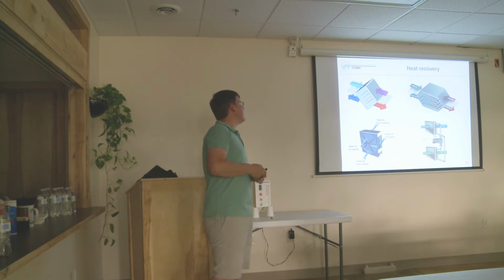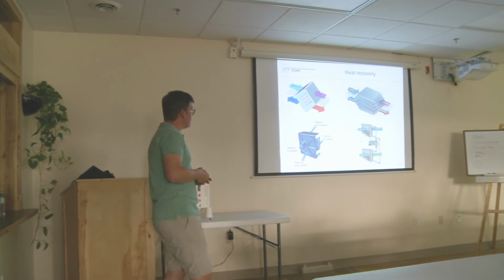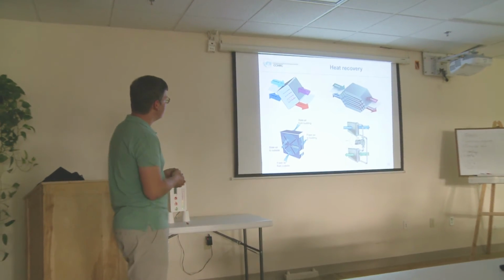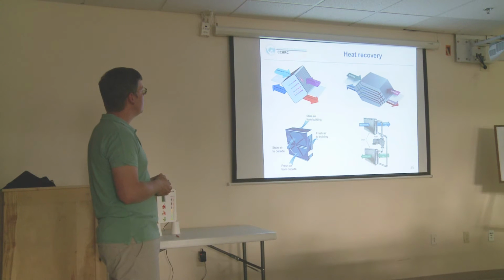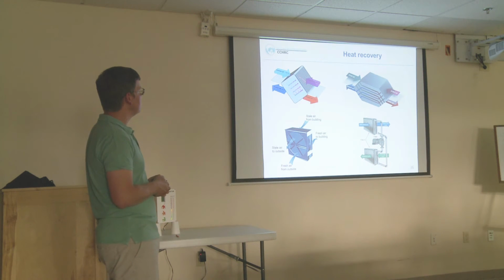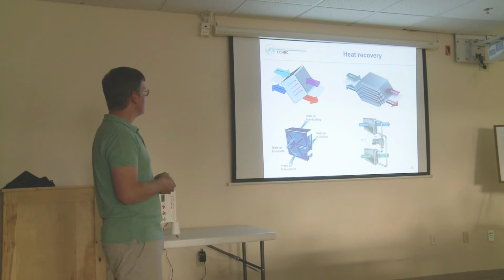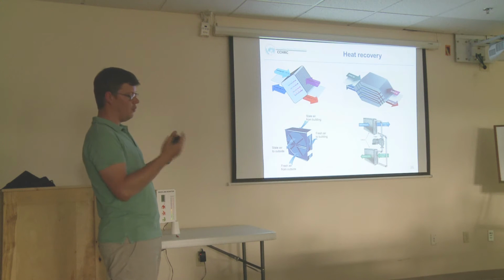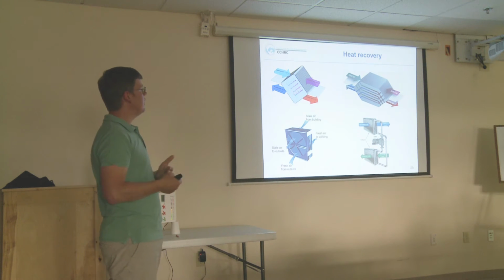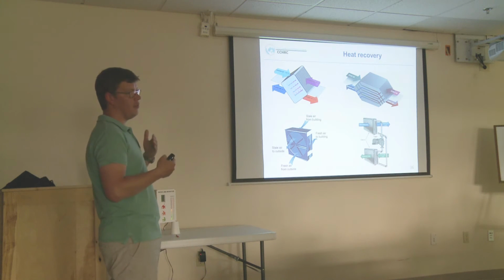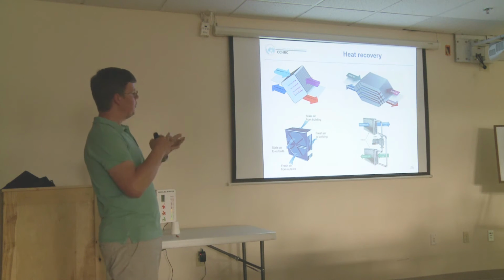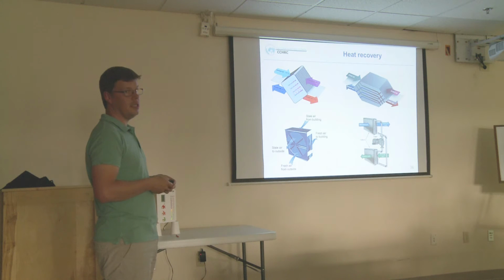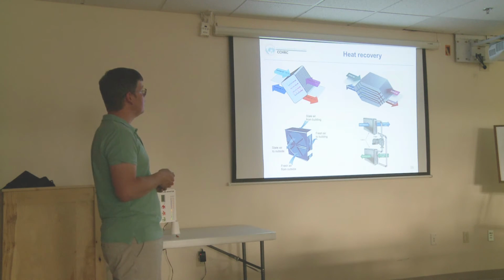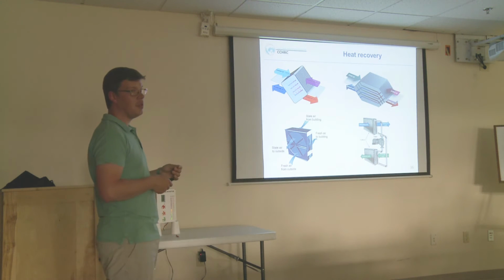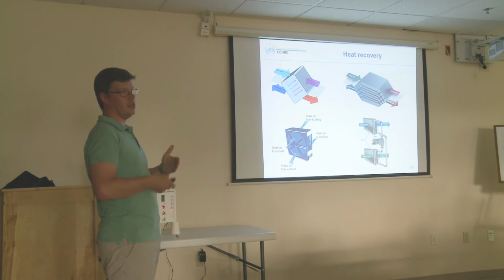The heart of the ventilation unit is the heat recovery core, and there are several principles for how that could be made. The most common here in Alaska, or perhaps in the US, is the flat plate heat exchanger, and that's nothing else than just a set of membranes or plates, where in every even plate there is the exhaust air, and in every odd plate there is the fresh air. As they pass through the plates, they exchange the heat. If it's a membrane material like Gore-Tex, for example, then the moisture could also travel through the membrane or through the wall, and that's how the moisture recovery is done.